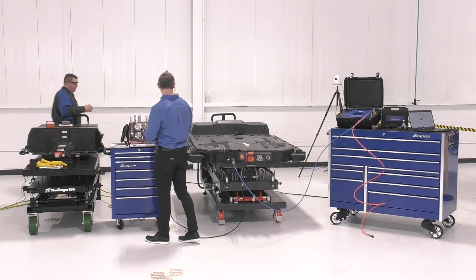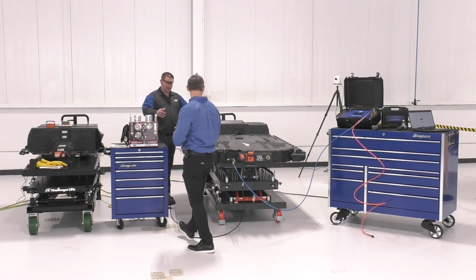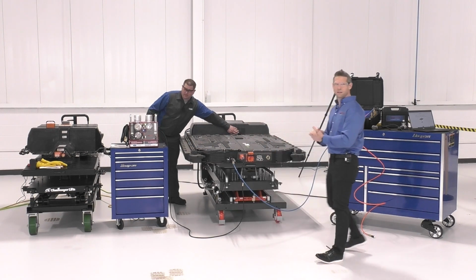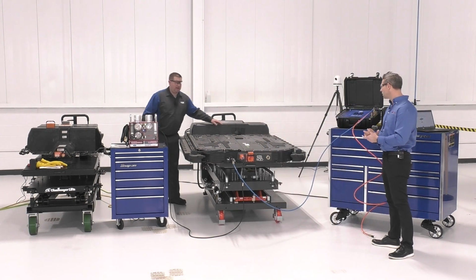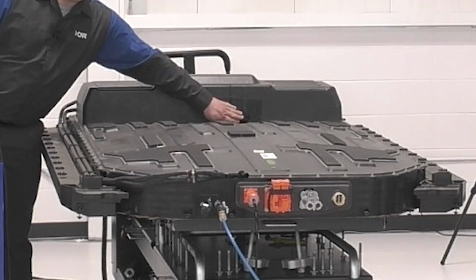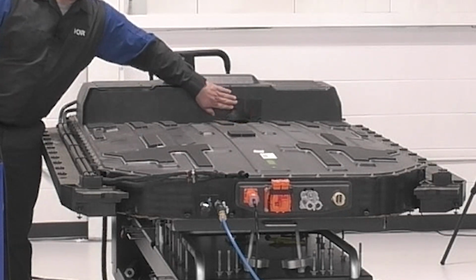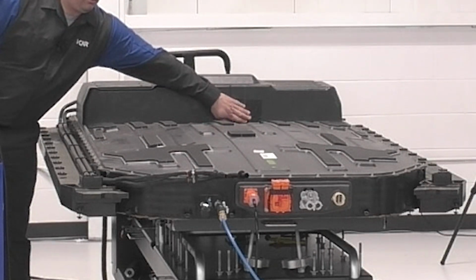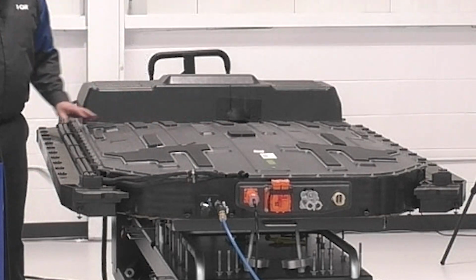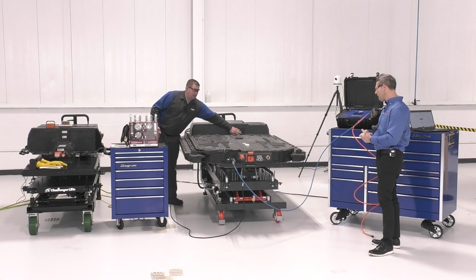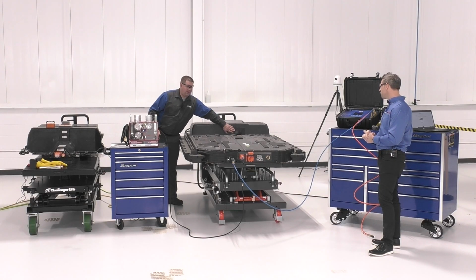If we can zoom in on that vent patch we were talking about earlier. There's actually a vent patch on top of the battery here, where it allows it to breathe a little bit, right, Chuck? Correct. So we have to do something. In the Ford service procedure, they tell you to put a Band-Aid over the top of the vent patch so we don't destroy it. Then we're going to put tape over the top of that to seal it off. And that way this vessel is now sealed.